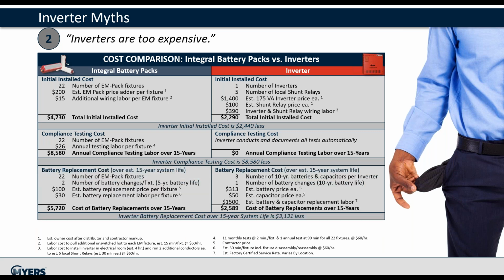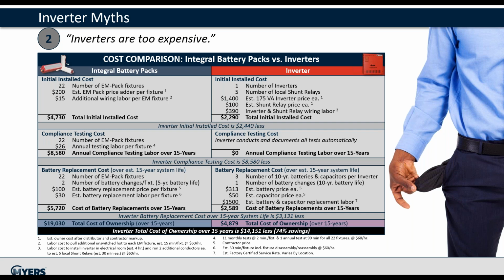The final piece of the puzzle is the replacement cost. The batteries for the battery packs are changed every 5 years, so there are 2 change-outs of batteries and the life cycle cost of $5,720. The inverter batteries are changed once, and a few electronic components, for a total cost of $2,589 over the 15-year period. In summary, the inverter system is the initial lowest cost solution from the start, and the total cost of ownership is about 25% of the integral battery pack, or a 75% savings.